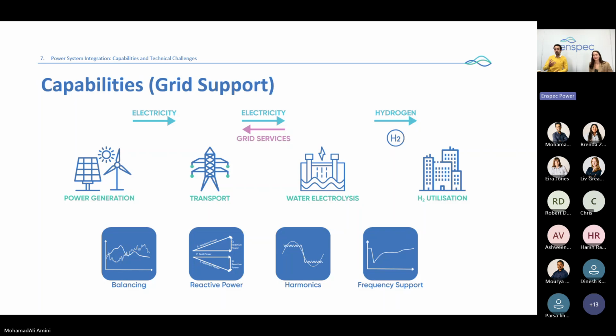Hydrogen electrolyzers are mainly there to produce hydrogen for downstream hydrogen users. In addition to their main obligations, they could provide some services back to the grid. As mentioned before, the main service could be load balancing for high penetration of renewable energy sources with intermittent natures. Hydrogen electrolyzers could also provide voltage support services through injecting or absorbing reactive power, as well as harmonic support and mitigation at the point of connection. More ideally, they are also capable of providing frequency support to the grid by participating in appropriate ancillary service markets.